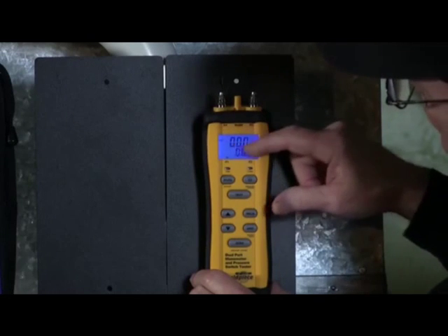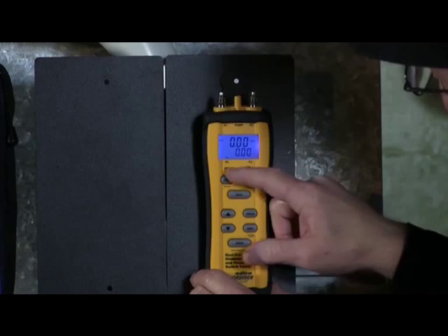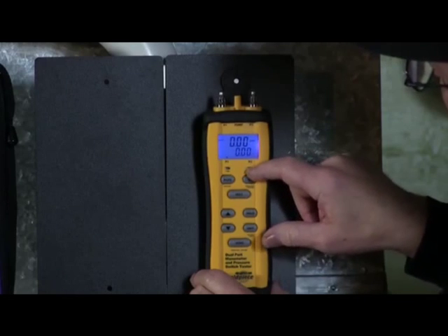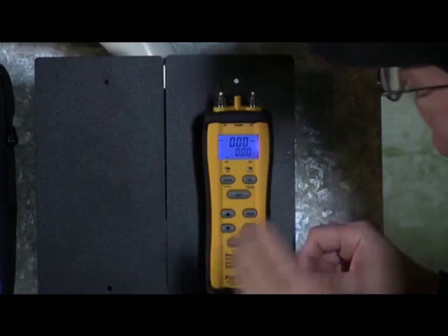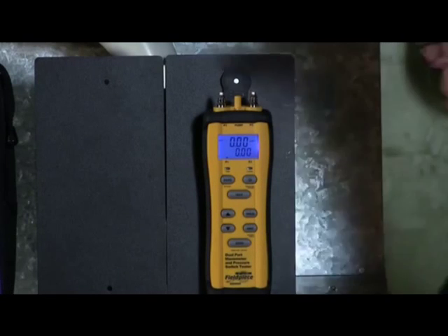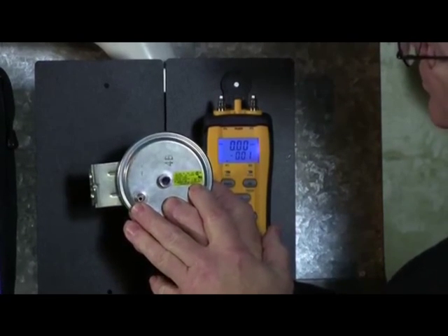This particular pressure switch is an inch and a half pressure switch, 1.50. But you'll note that it does say WCPF, which is inches of water column pressure fall. That means it's supposed to open at 1.50. It should close around there as well, but you have a 10% variance, so it would still be okay if it closed at 1.65 or opened at 1.35. That would be within 10% of this switch.